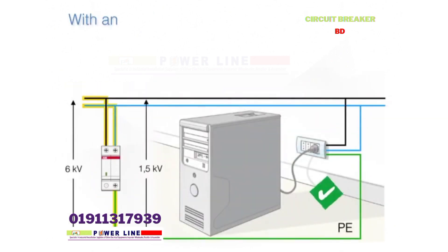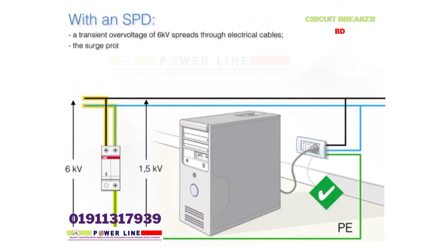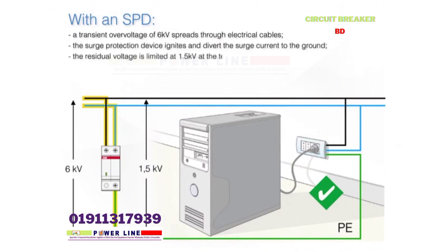With an SPD, a transient overvoltage of 6 kilovolts spreads through electrical cables. The surge protection device ignites and diverts the surge current to the ground. The residual voltage is limited at 1.5 kilovolts at the terminals of the SPD. The server is on the safe side and protected from the overvoltage.